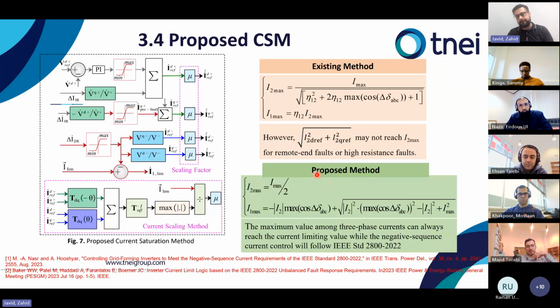It works well for near end faults or low impedance faults, but for far end or high impedance faults, the equation shown here may not reach the I2 maximum, so it may not strictly align with the standard. We have modified the strategy by setting a hard limit in the sequence domain: I2 max is equal to I max over 2, and then we calculate I max with this equation. This ensures that it strictly follows the IEEE Std 2800-2022.